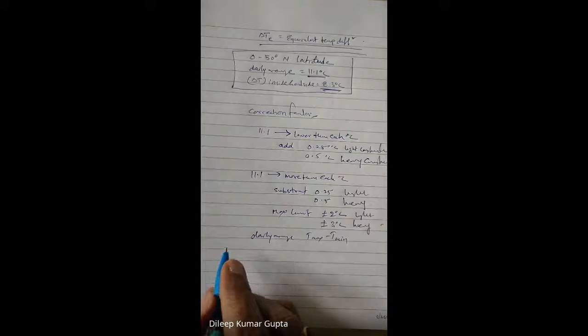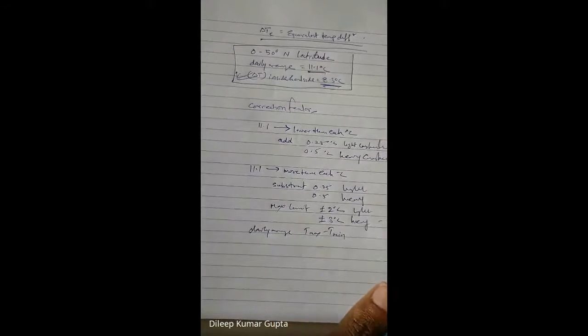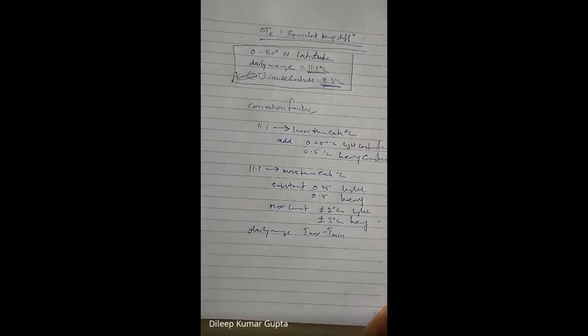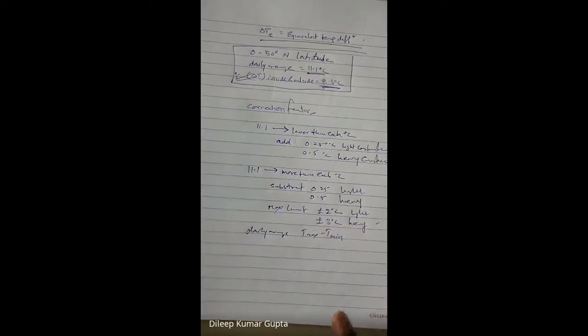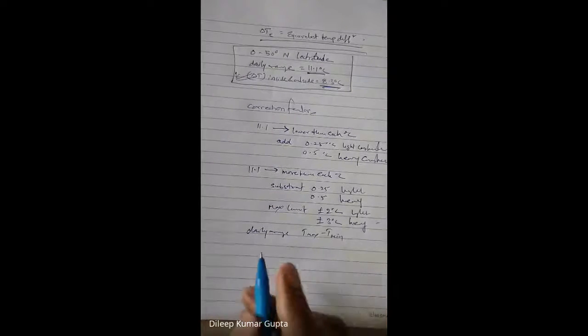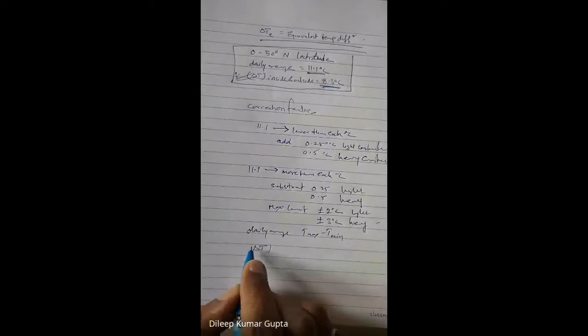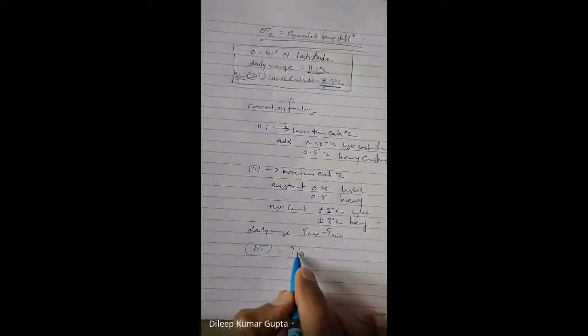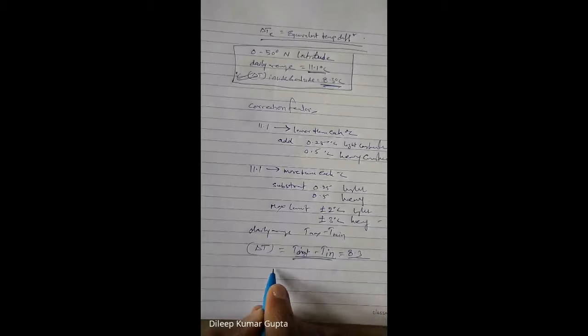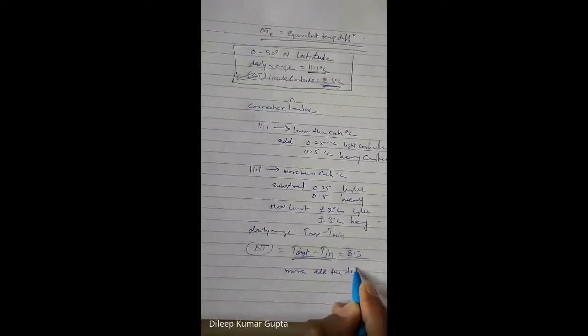This is one thing. Second thing is delta T of inside and outside. This will not always be the same because outside condition is varying. Even though you can keep the inside condition same, the outside condition will not be same always. So this delta T, we are talking about design point, right? So this delta T with respect to design point, whatever the value of plus or minus is there, so delta T, T out minus T in, if it is equal to 8.3, fine. If it is more than 8.3, then you have to add that much in the actual. If it is more, then add the difference. If it is less, then subtract the difference.